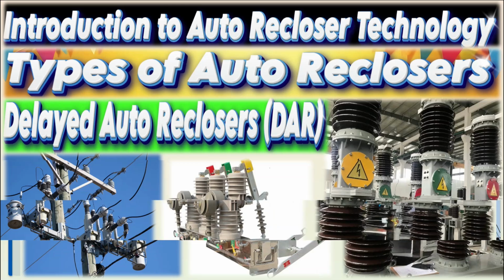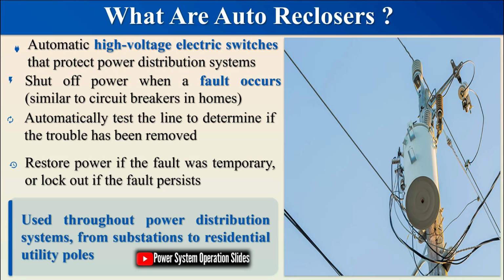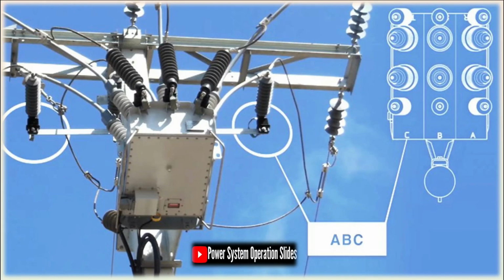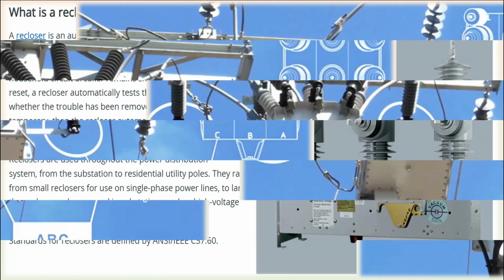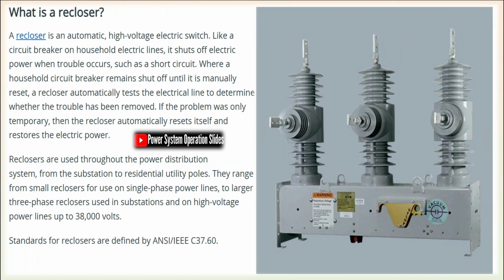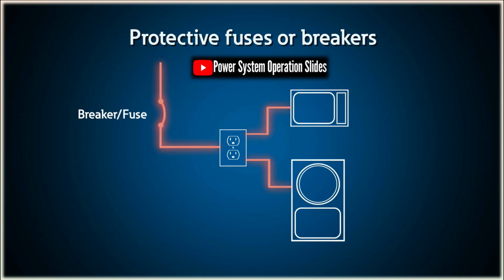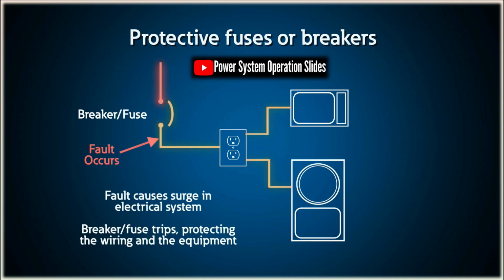Auto reclosers are automatic high-voltage electric switches designed to protect power distribution systems. Similar to circuit breakers in household electrical systems, they shut off electric power when a fault occurs, such as a short circuit. However, unlike household circuit breakers that remain shut off until manually reset, auto reclosers automatically test the electrical line to determine whether the trouble has been removed. If the problem was only temporary, the recloser automatically resets itself and restores electric power.